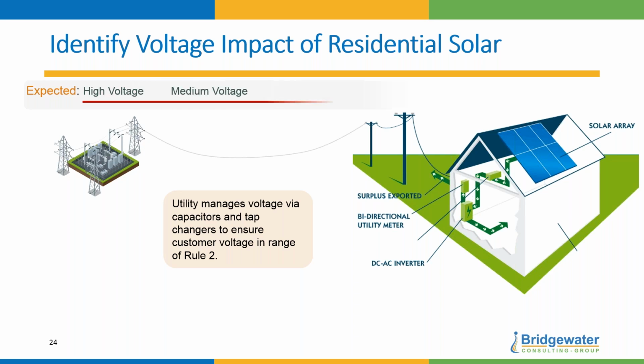What do we always expect? For years and years, we saw high voltage at the substation, going down to medium voltage, and then low voltage in the neighborhood, basically due to I squared R losses in the conductor and heavier loads. So what you do is increase voltage at the capacitors, trying to boost the voltage at the neighborhoods.